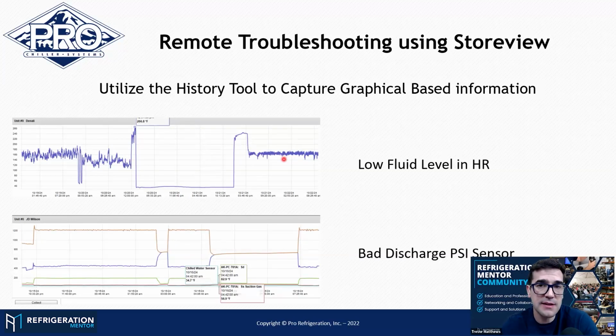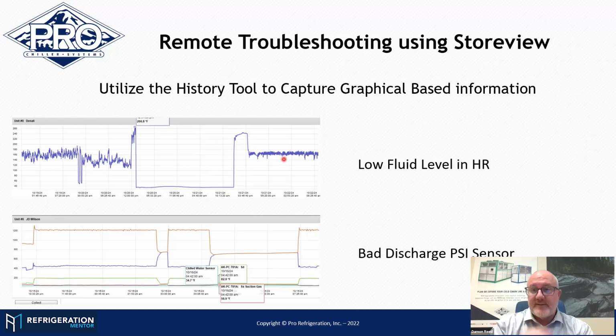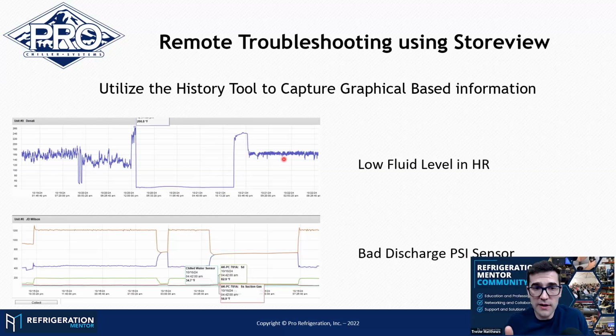And this is the biggest thing that I see in secondary glycol systems, liquid overfeed systems, where us as refrigeration technicians, even chiller technicians, we get focused on the refrigeration circuit, but this has nothing to do with the refrigeration circuit to cause this trip. Correct. Even doing this remotely, looking at this remotely, you probably couldn't tell that's the low fluid unless you're there and you actually do the tests and checks and look for a leak.